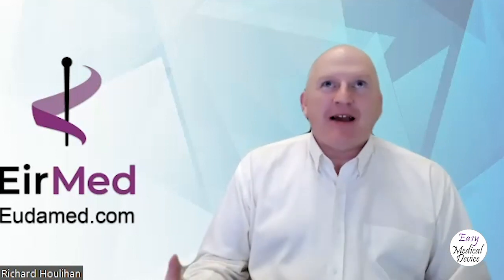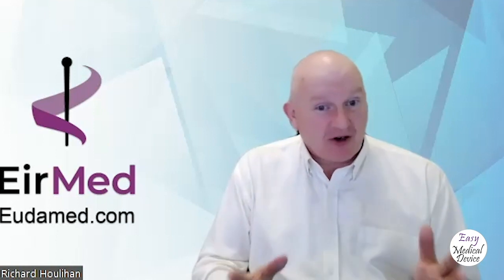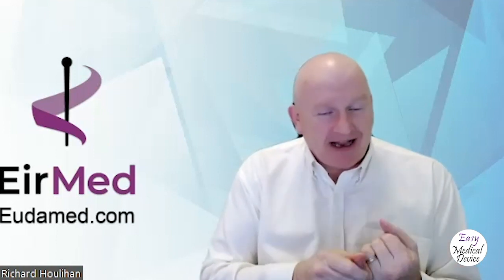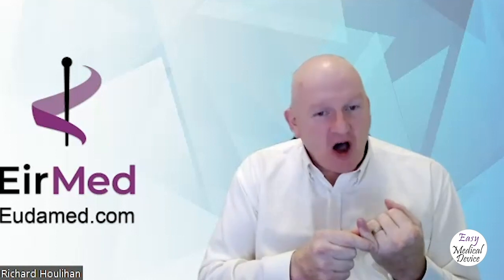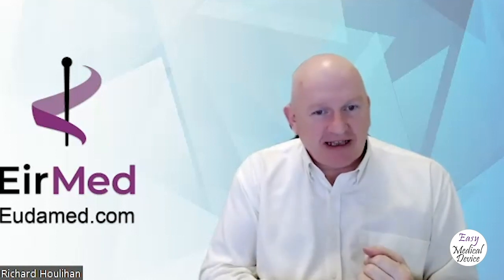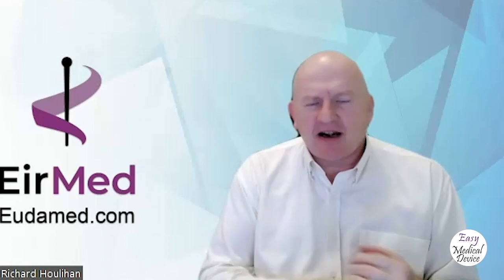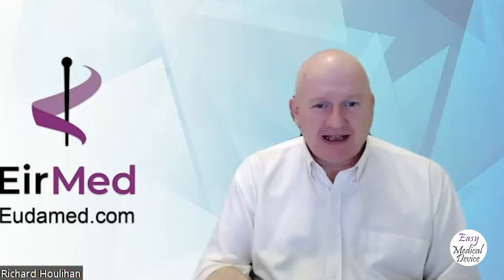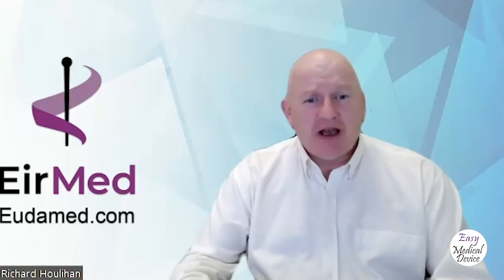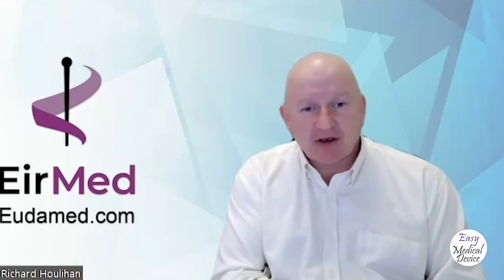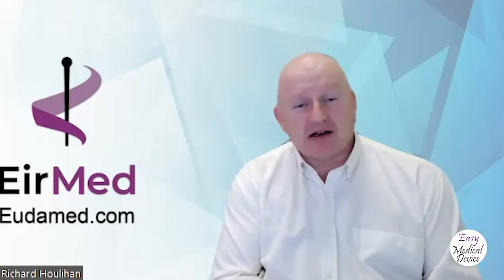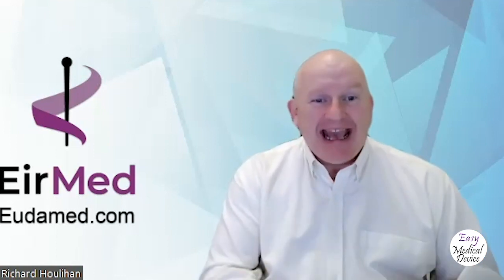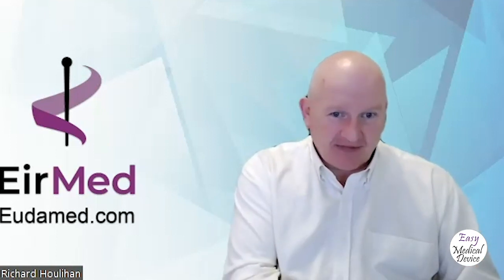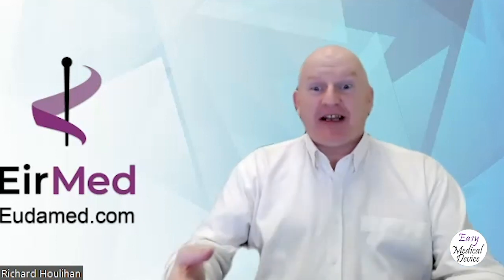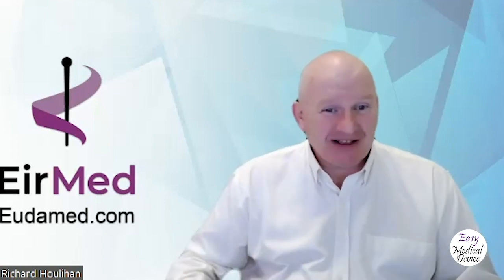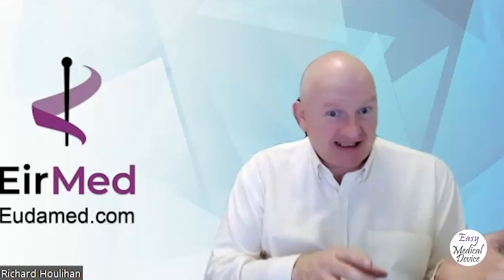Now, you may wonder, why would anybody want to play with EUDAMED? There are several good reasons. First of all, upload your XML files to the playground first. If you've got loads of mistakes in there, nobody sees it. Exactly. Nobody sees it. It's only you. The competent authority will not come to you because you did something horribly wrong inside your XML on the playground. It's only your data. You don't get any emails from the playground. Even when you get approved for your SRN, you don't get any emails from it. There's nothing that comes out of this. So that's the first thing.